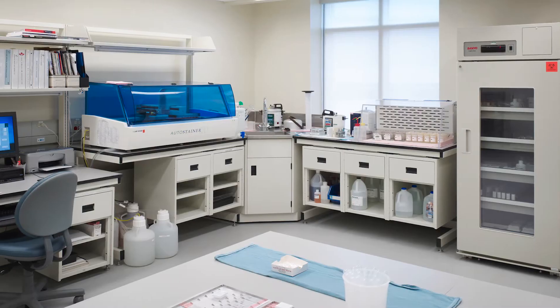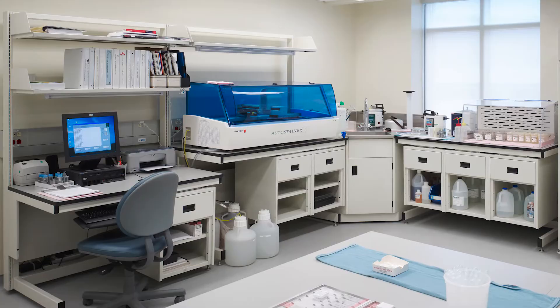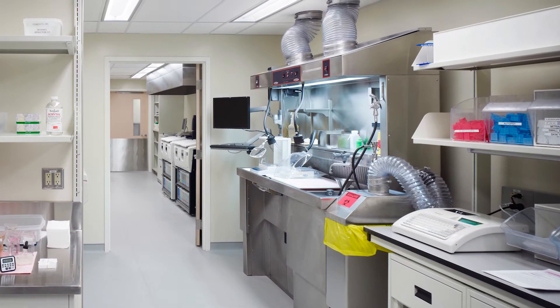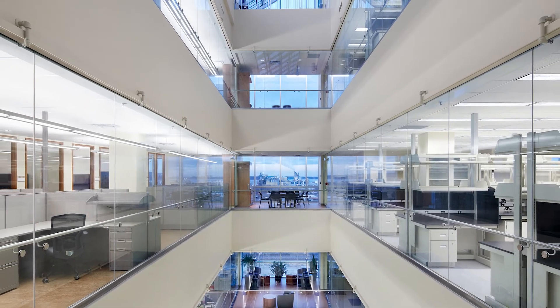The other important part of getting scientists to talk together was creating collaboration spaces. The way laboratories are designed, you have a place to do your dry work and a place to do your wet work. Laboratories are very expensive to operate because they're traditionally designed for the worst-case scenario — so if there was a spill in the laboratory, you'd need the air to evacuate quickly, with 8 to 12 air changes in that space. What lab designers have been doing recently is keeping office space on one side and laboratory space on another side, either across a hall or in a separate building but somehow interconnected. The clever way to do that is to create a collision space in that link — just creating opportunities for scientists to talk to each other to advance the science.